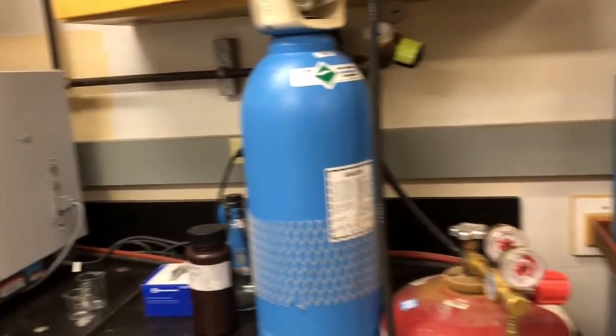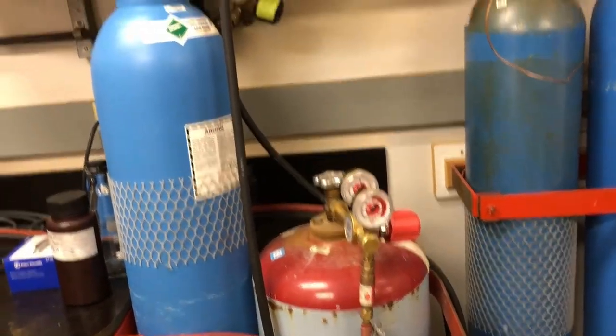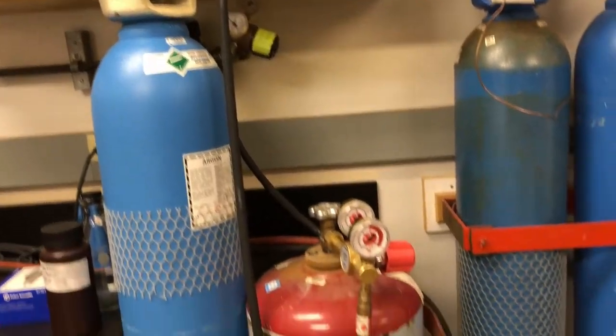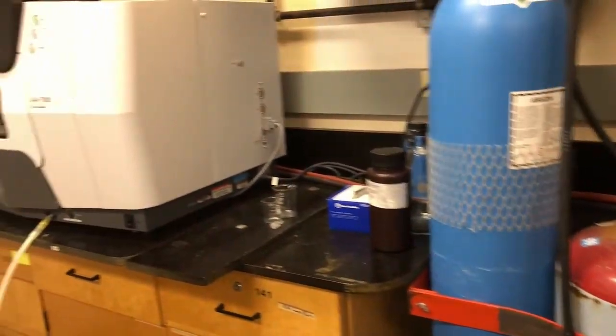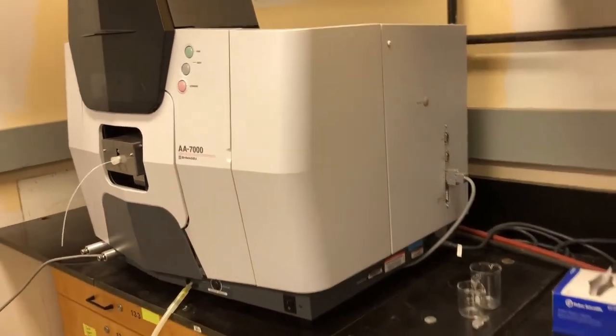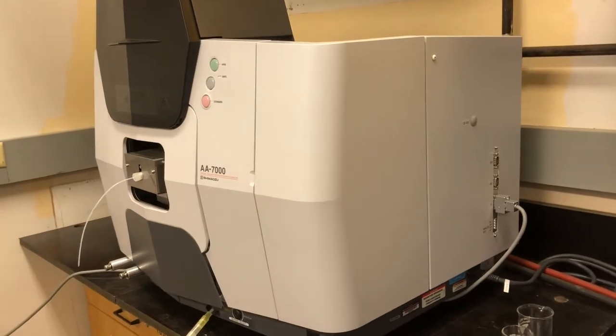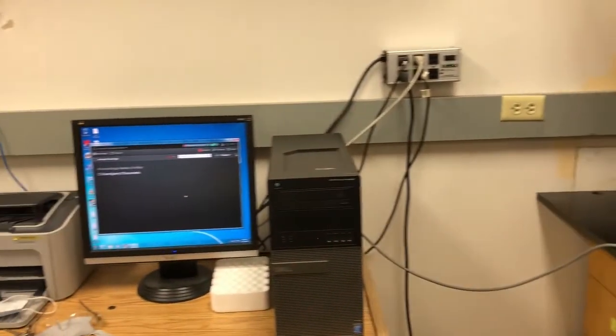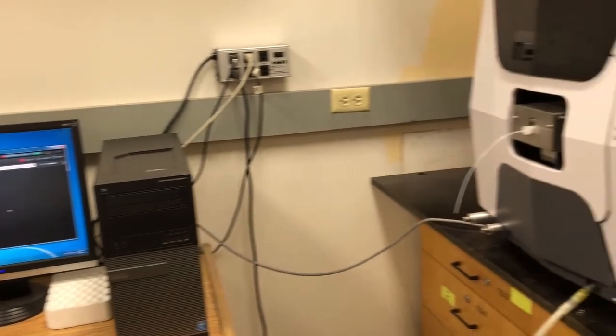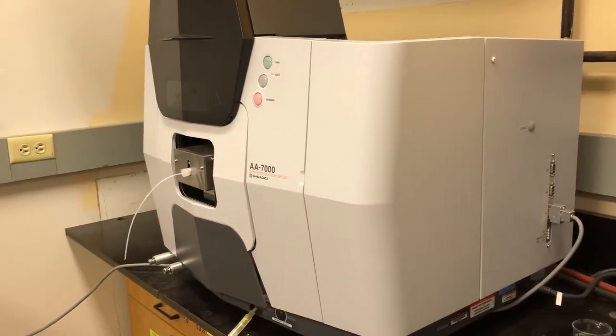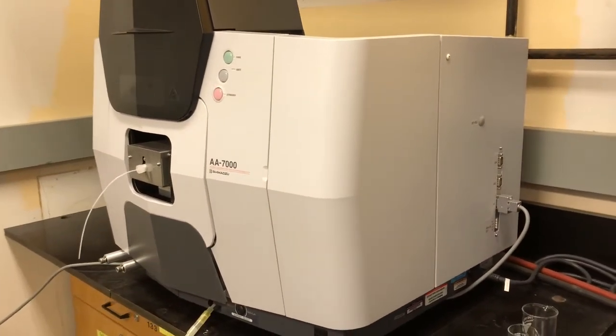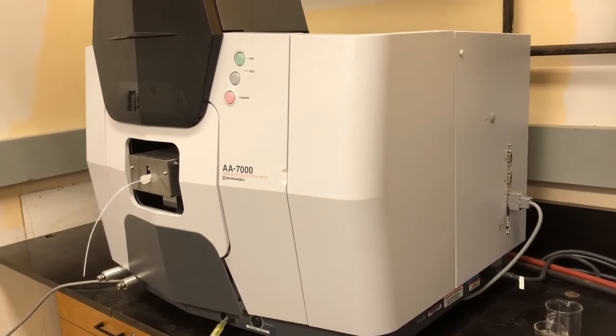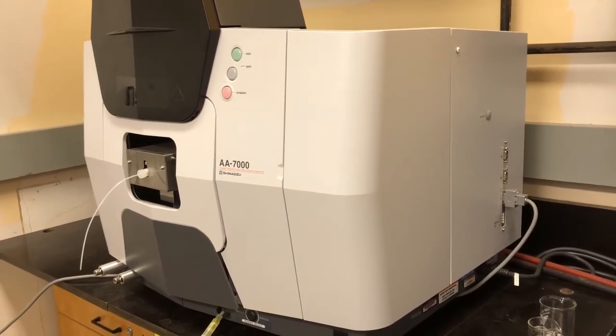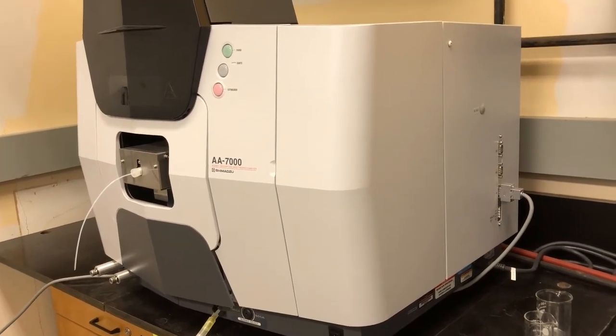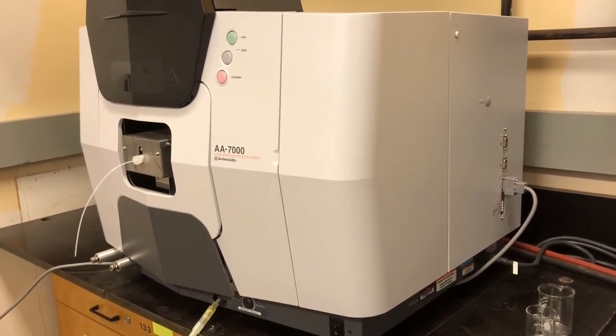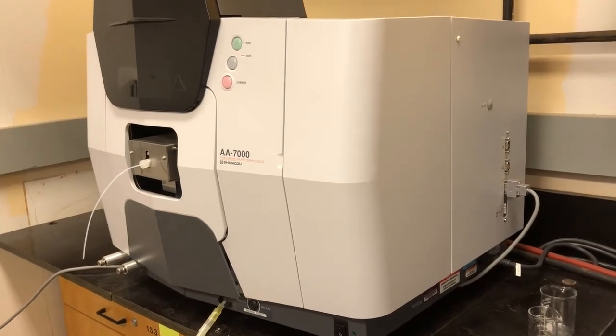So we have acetylene and air over here. That supplies the fuel to ignite the flame. Everything else on the instrument is controlled via computer. We have a computer over here that we use to set up the machine, so it contains the AA software that we can use to set all the parameters that we need for our sample analysis. So now we're going to go over to the computer and get our machine set up and ready to run our iron standards and samples.